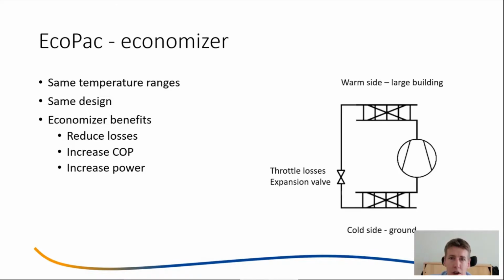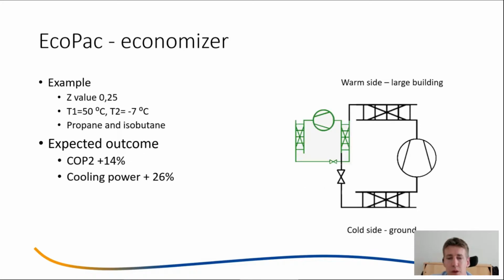Let's say we have a larger heat pump that on the cold side is connected to the ground and on the warm side is connected to a large building. Then one of the major losses in this system is the throttle losses in the expansion valve. One way to reduce these is to connect another heat pump, or an EcoPac, so that we subcool the liquid even more than it's subcooled after the condenser, so that it's more subcooled before it enters the expansion valve.